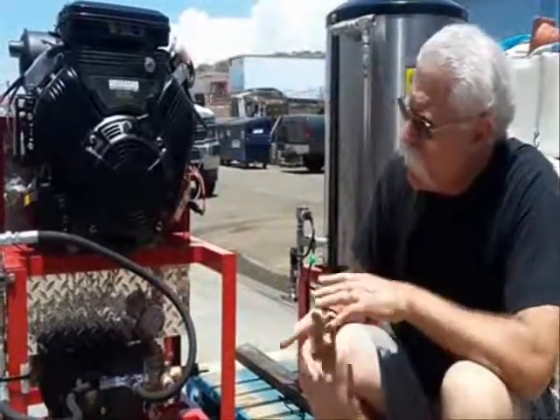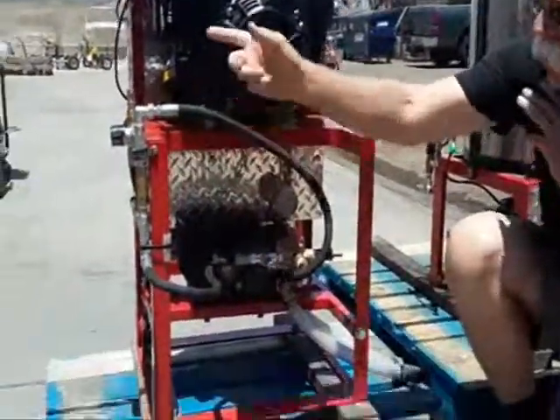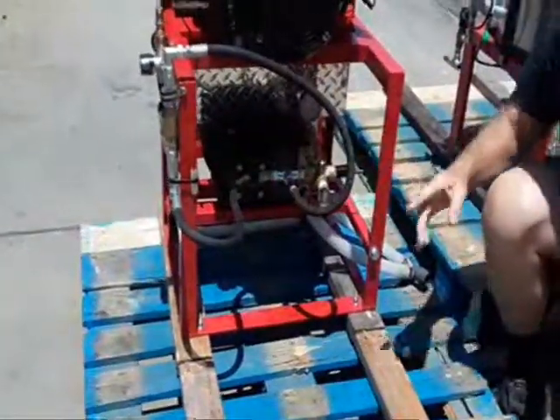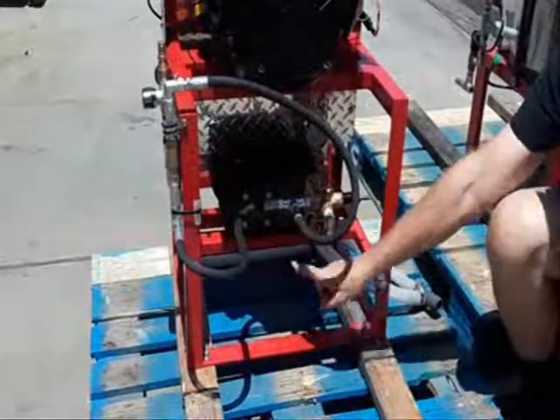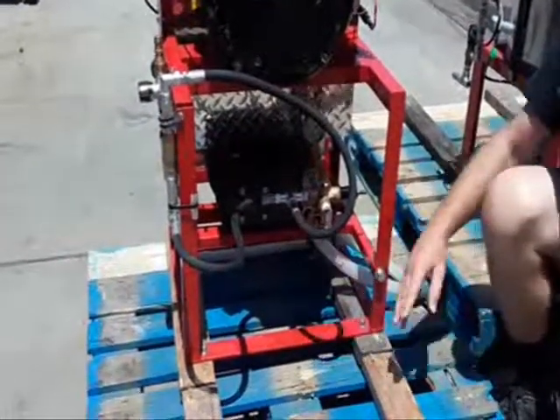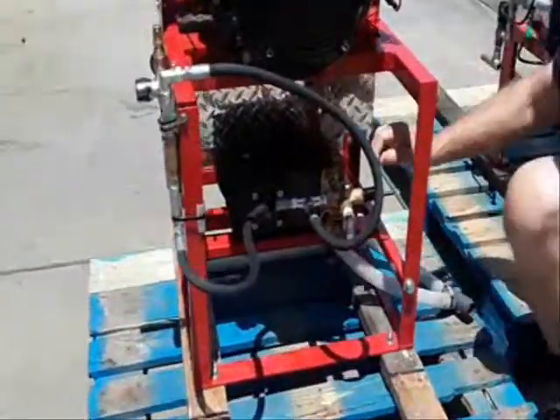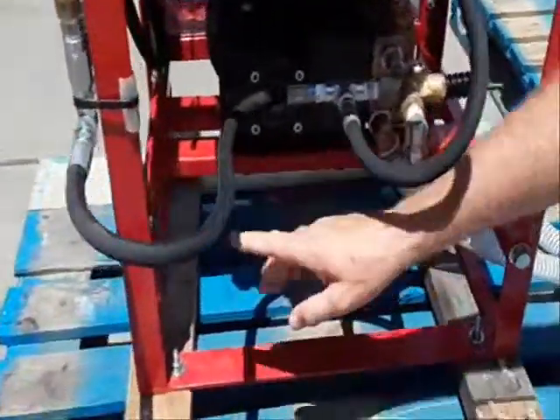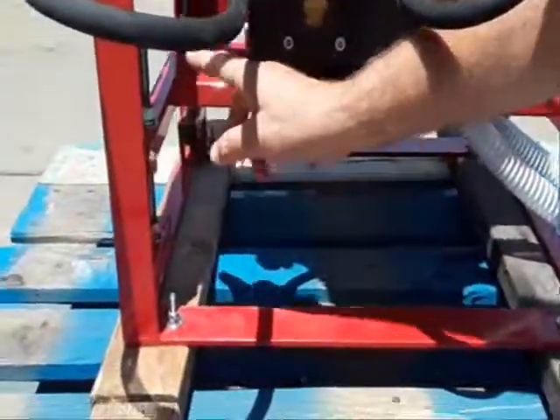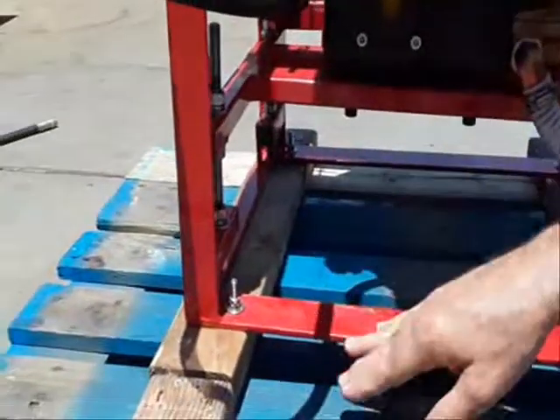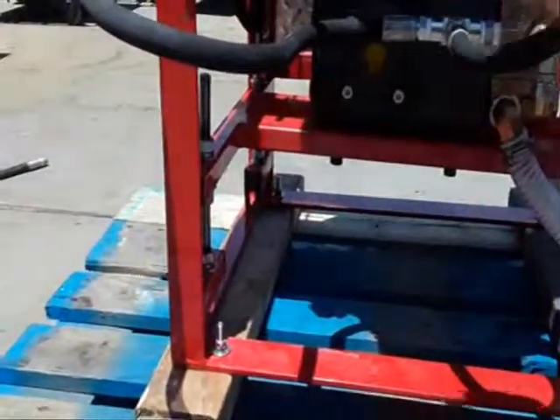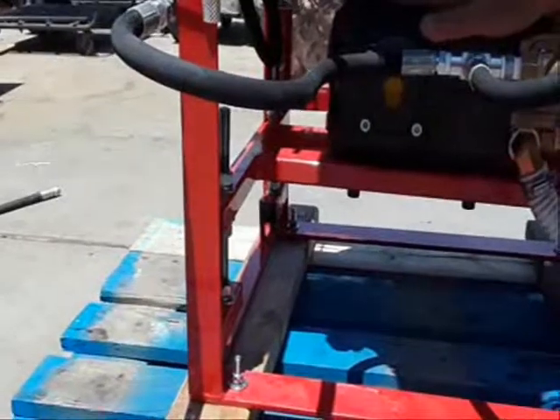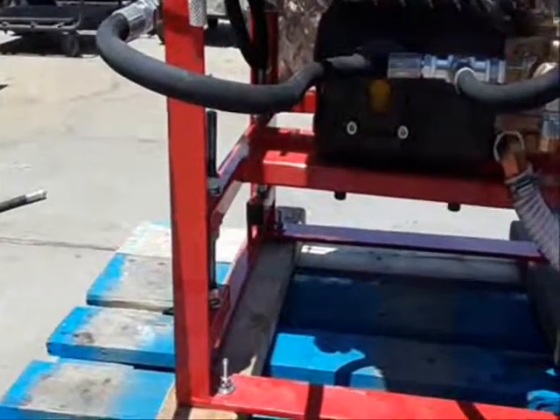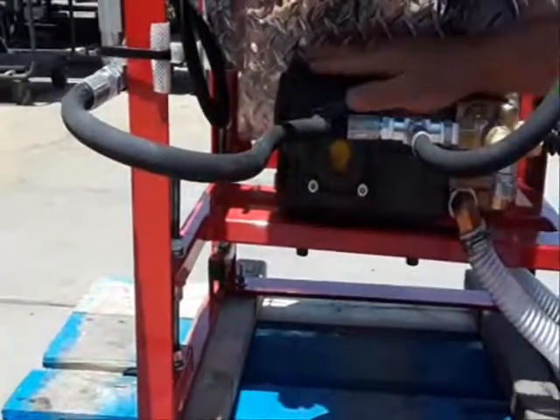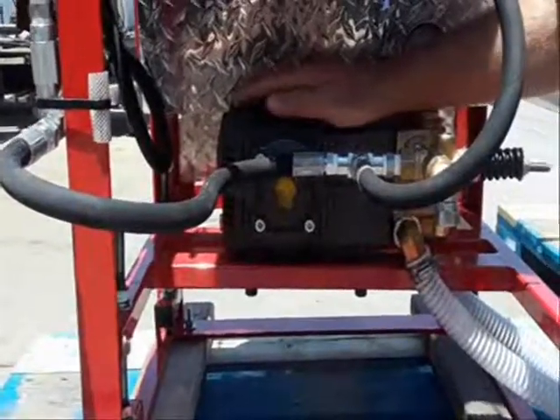Okay? So secondary regulator, separate bypass back to the tank. Primary regulator, separate bypass back to the tank. Okay, this is belt drive. This is on a swing arm configuration. You've got 2 bolts here that operate the swing arm. So you want to loosen this and raise the thing up when you want to change the belts or tighten the belts. You just tighten it back down again when you want the belts tight. This is super simple to service.